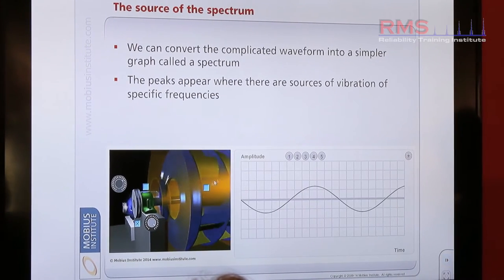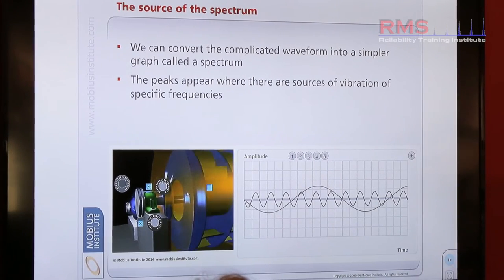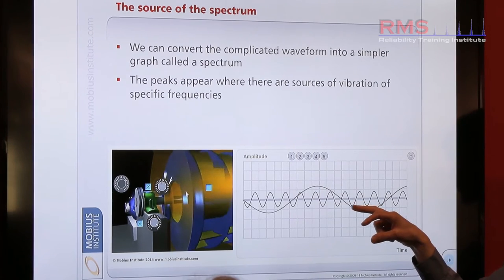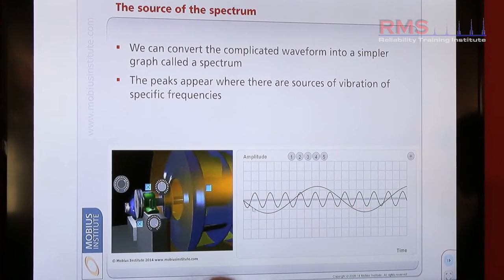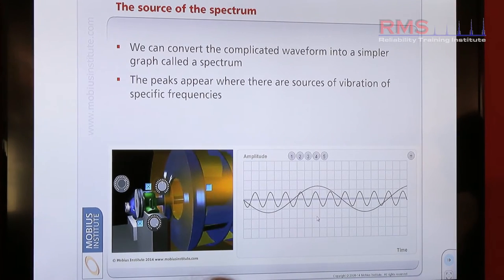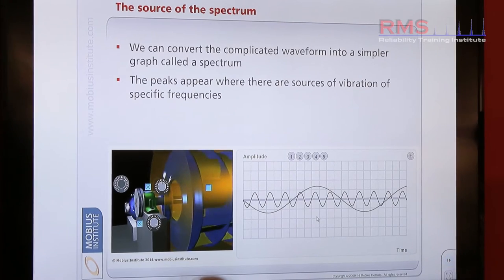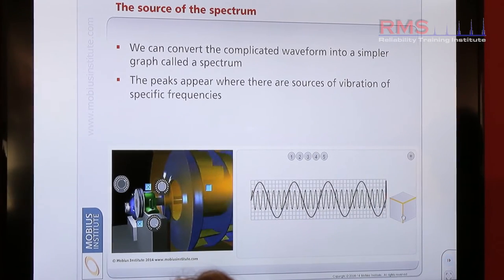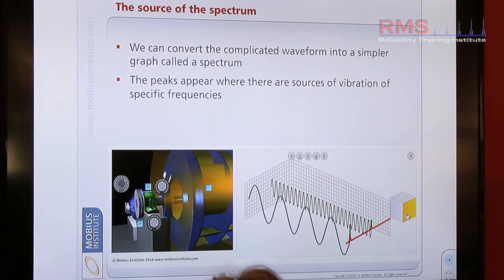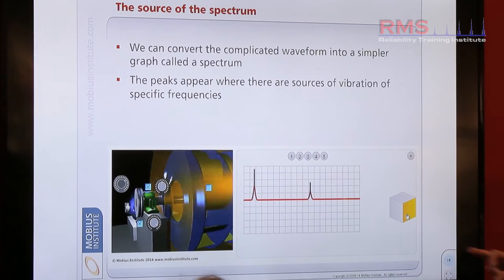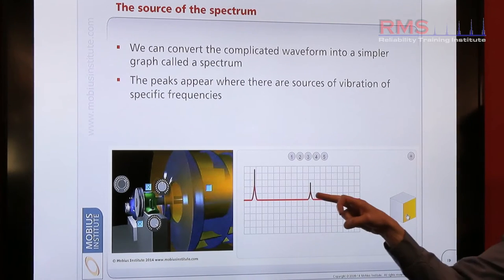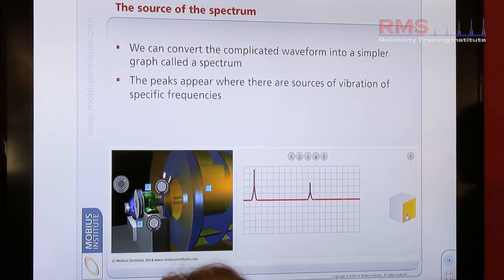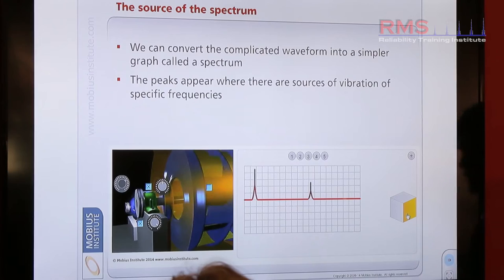Let's switch it back and maybe the bearing here has a defect — a pitted spall point on the bearing. In one rotation there'll be a certain number of pulsation forces every time a ball strikes the bearing. Count the number of pulses there. Higher frequency, yeah? So the green wave is the heartbeat of the bearing. Let's bring that together. What do we see? Two separate peaks — one proportional to rotational speed from the unbalance in the fan, and one that shouldn't be there because there shouldn't be a problem with the bearing, but it's appeared at 6.1 times the speed. Not six, not seven, but 6.1 times the speed. So that's a key difference for the bearing — it's actually not a whole number.